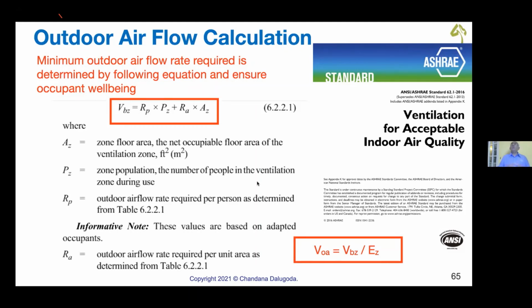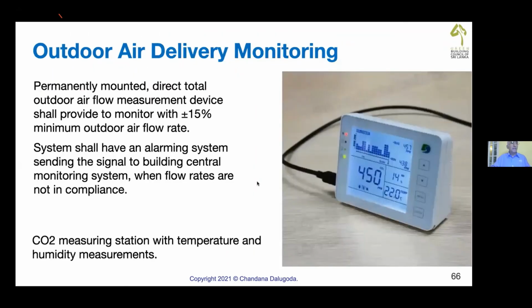Now the question is, outdoor air is at 32 degrees C with a large moisture content. Usually in Sri Lankan weather, 20 grams of water vapor in 1 kilogram of air. For comfort conditions, we'll have to drop it to 10 grams of water vapor per 1 kilogram of air by the air conditioner. Now all these need energy. That means supplying outdoor air means energy. You need a large air conditioner. So you'll have to mitigate this. How to mitigate? You'll have to use treated fresh air units or energy recovery ventilators.